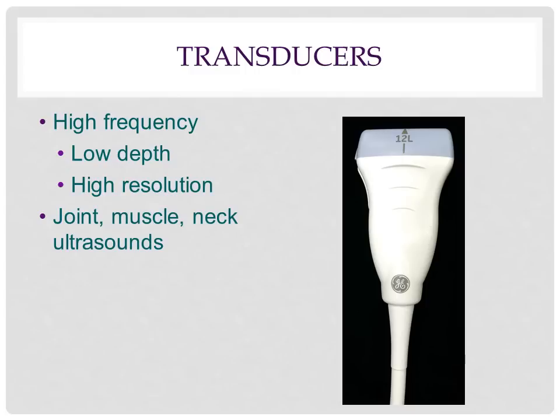Lastly, the 12L transducer probe emits the highest sound frequency. While the images are much clearer than other probes produce, it cannot transmit sound waves deep into a cavity. For this reason, 12L probes are best suited for joints and superficial anatomy.